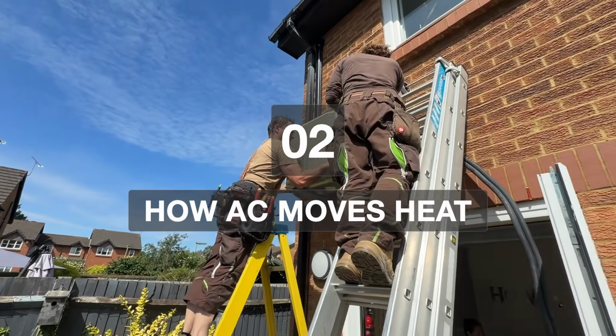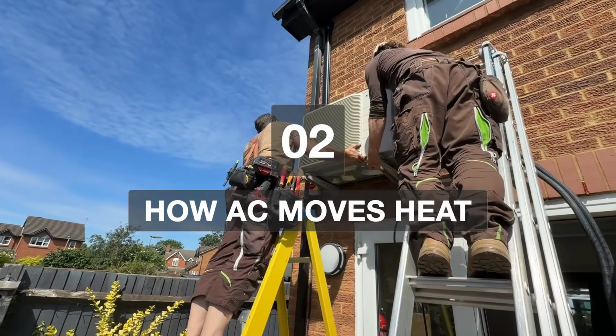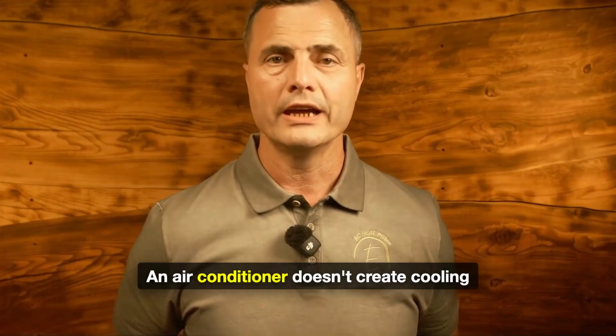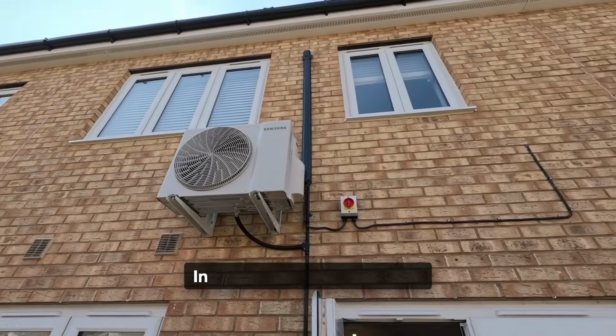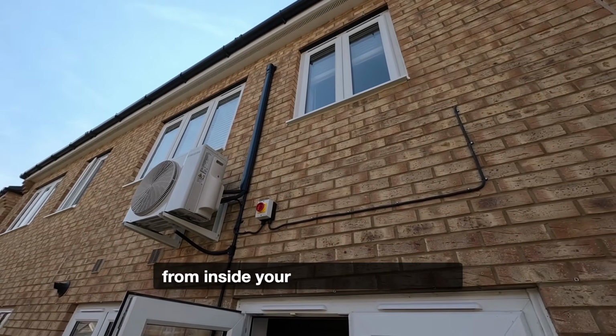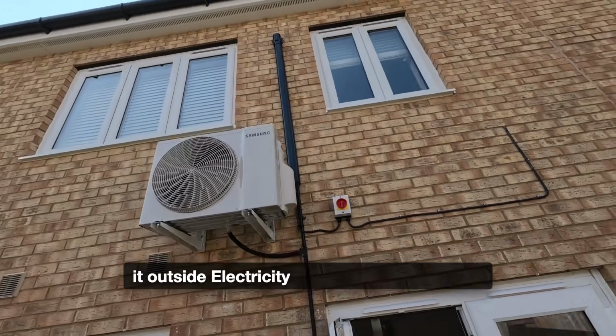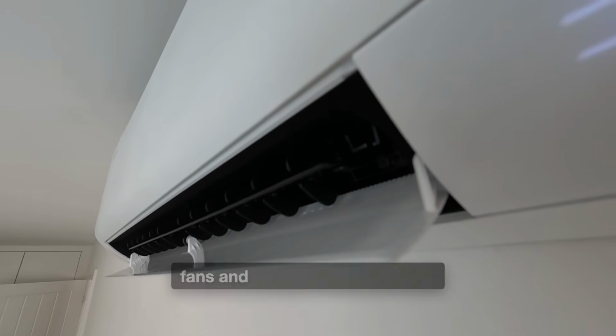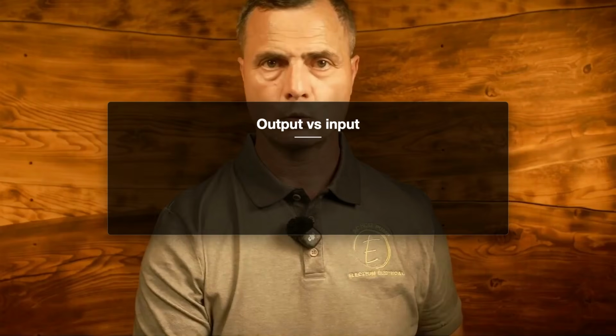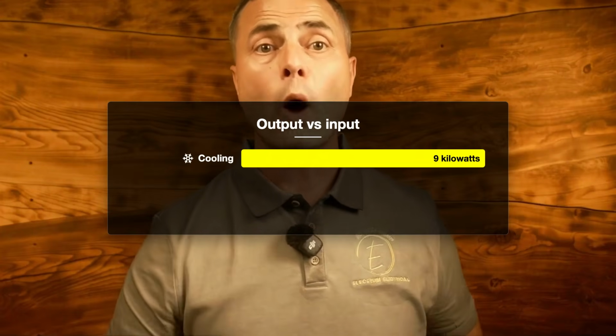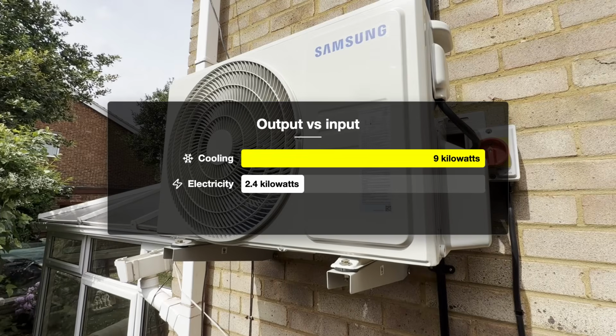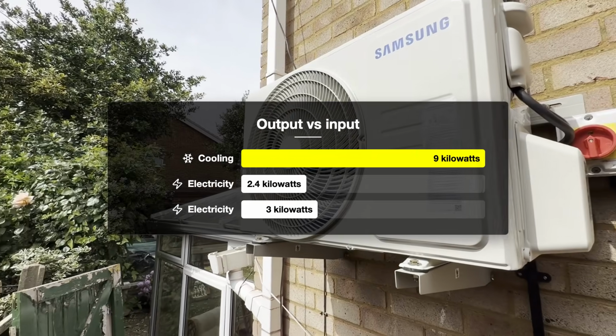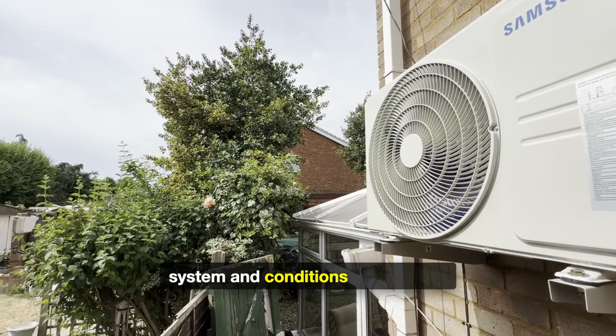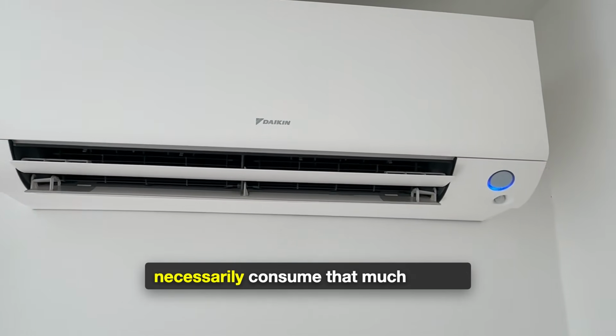Section 2. How can 3 kilowatts of electricity produce 9 kilowatts of cooling? An air conditioner doesn't create cooling, it moves heat. In cooling mode, it takes heat from inside your house and transfers it outside. Electricity powers the compressor, fans, and controls that make this possible. That's why a system can potentially deliver around 9 kilowatts of cooling while consuming somewhere around 2.4 to 3 kilowatts of electricity at substantial load, depending on the system and conditions. And it won't necessarily consume that much all day.